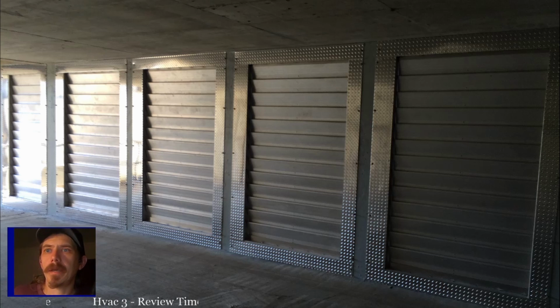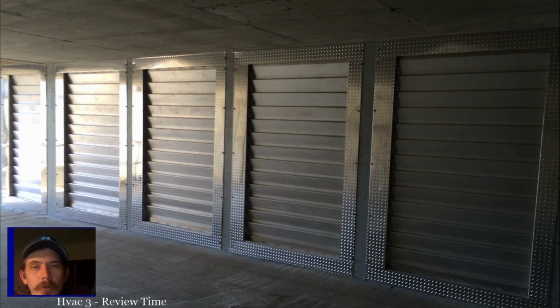The other thing that you need to understand is the winding resistance to ground on an ECM. So if you're checking for a short to ground, all right, again, all three windings should be the same. All three windings should be very close to exactly the same in an ECM. All three windings should have the same resistance. If not, if one is open, you get OL, then that's an open winding. If you get a dead short, you read 0 from one winding to the other, then there's a dead short on a winding.